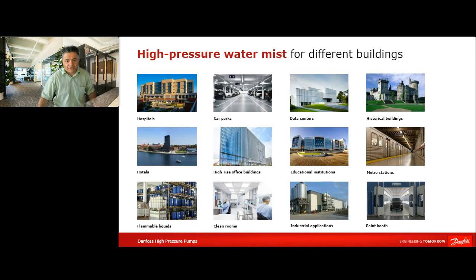When we talk about high pressure water mist in buildings, we are not limited to data center buildings, but also many other applications or building types, as you can see here as an overview. Each building type has its own particularities, its own risks, its own special features that we need to pay attention to. But in the end of the day, all of them can be covered by a typical high-pressure water mist fire suppression system.